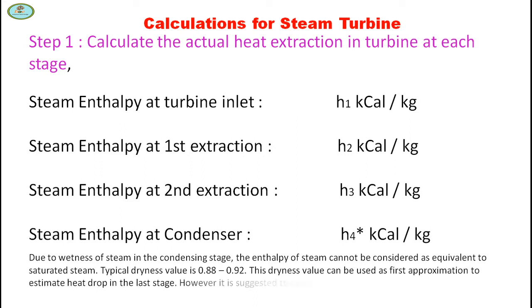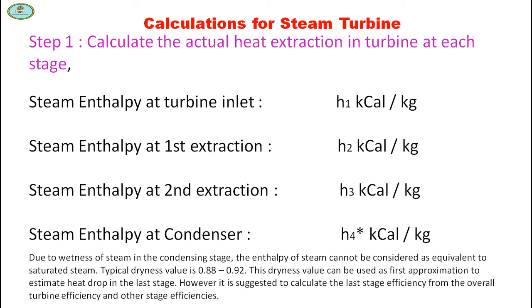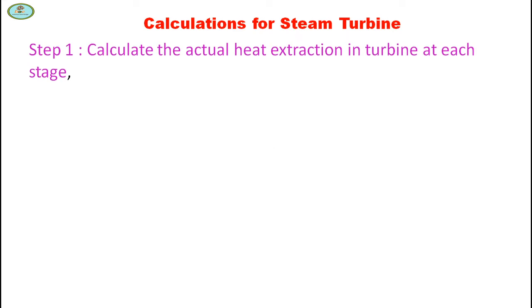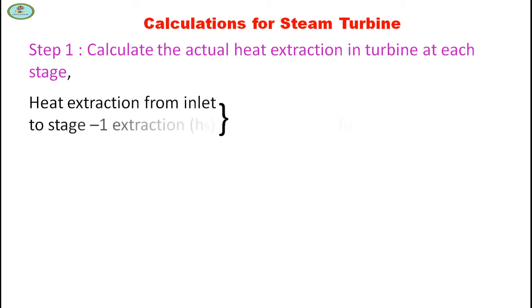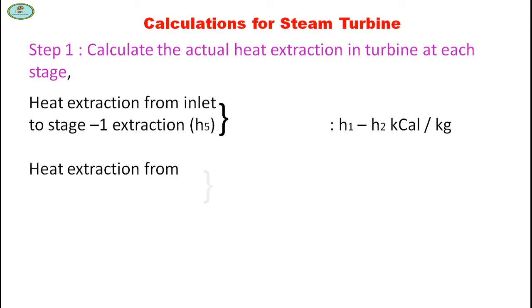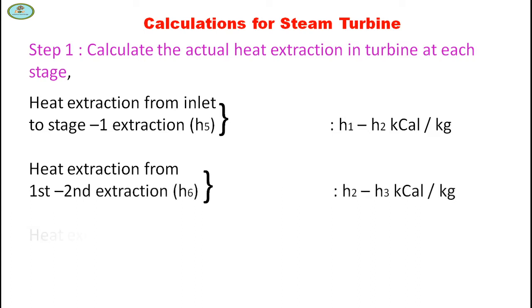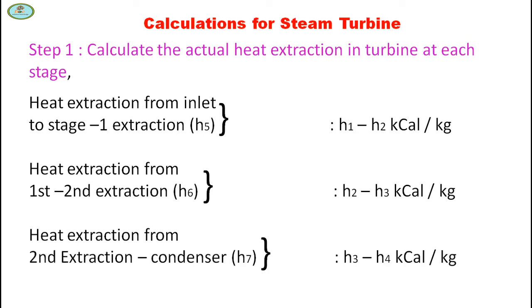This dryness value can be used as a first approximation to estimate heat drop in the last stage. However, it is suggested to calculate the last stage efficiency from the overall turbine efficiency and other stage efficiencies. Heat extraction from inlet to stage 1 extraction is H1 minus H2 kcal/kg, from first to second extraction is H2 minus H3 kcal/kg, and from second extraction to condenser is H3 minus H4 kcal/kg.